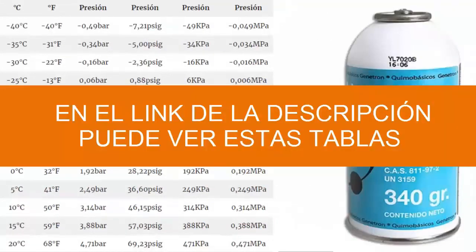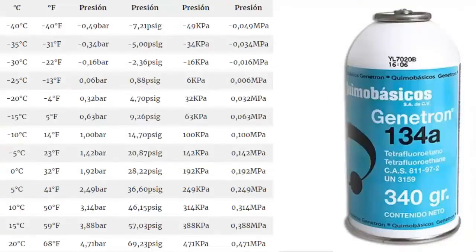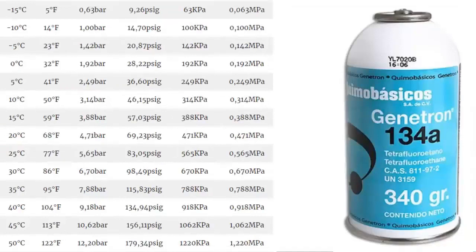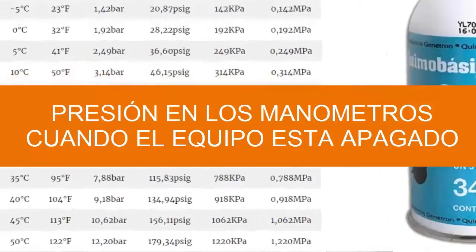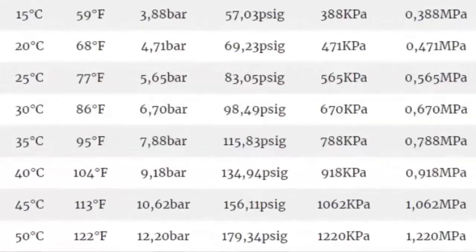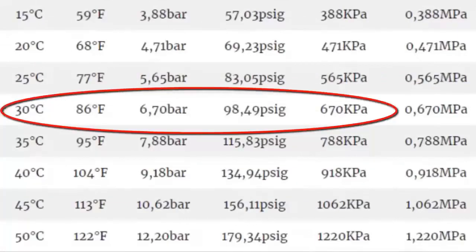In some cases, it is useful to know the pressure of the equipment when it is turned off, and the high pressure or the condenser. 1. For an external environment temperature of 30 degrees Celsius, with the equipment turned off, it has a manometric pressure — both high and low — according to the table of 6.70 bars, equivalent to 98.49 PSIG or 670 kilopascals.